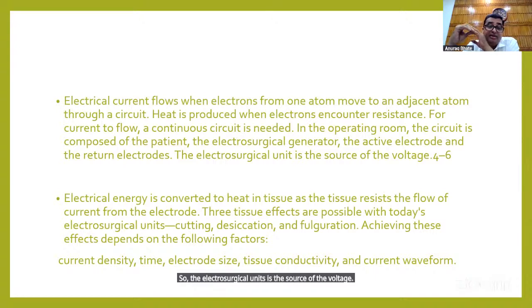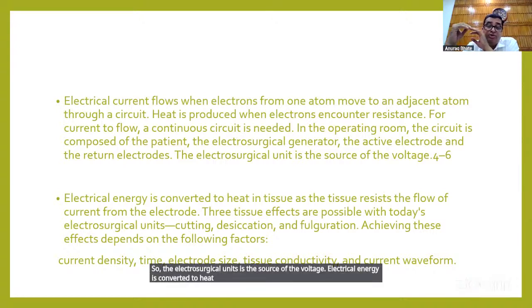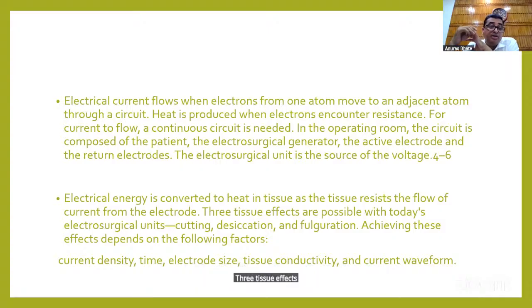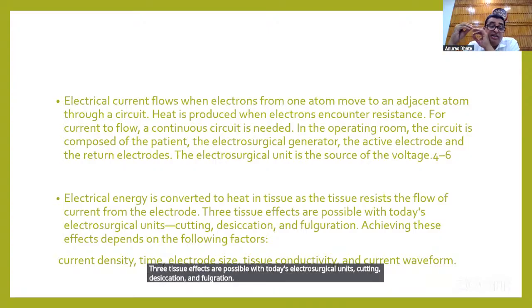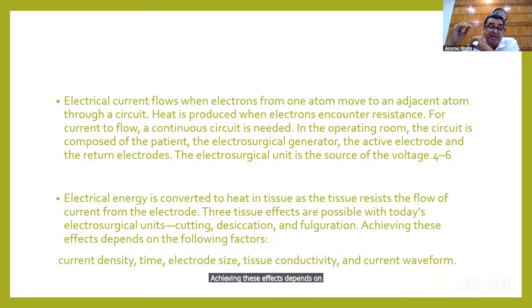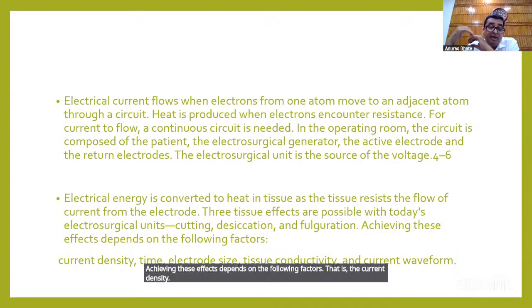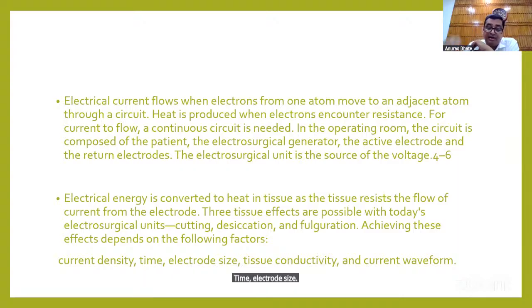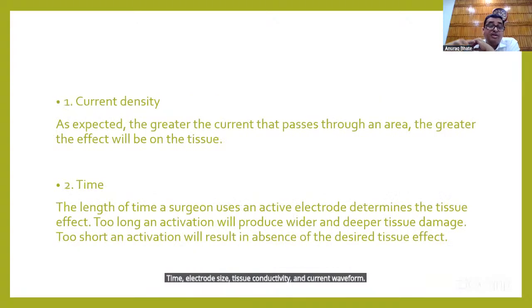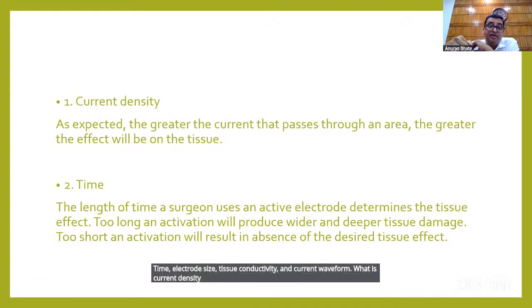Electrical energy is converted to heat in tissue as the tissue resists the flow of current from the electrode. Three tissue effects are possible with today's electrosurgical units: cutting, desiccation, and fulguration. Achieving these effects depends on the following factors: current density, time, electrode size, tissue conductivity, and current waveform. What is current density? As expected, the greater the current that passes through an area, the greater effect it will have on the tissue.